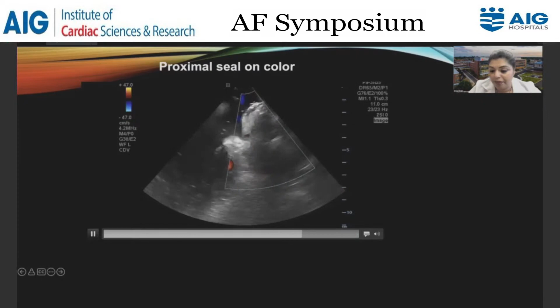So what proximal seal is, is that we get occlusion, we pull it off and get a leak, and then move forward as we're starting the freeze to make sure that we don't engage the vein too deep. So you can see, I'm going to go back in there. Here's the balloon. We're getting to inflate the balloon. 2/3 of the balloon is outside. You can see we have full occlusion here. I'm going to pull the whole system back now, and that's going to cause a leak. And then that's a proximal seal. I moved it forward to make sure that I'm not engaging the vein too deep.